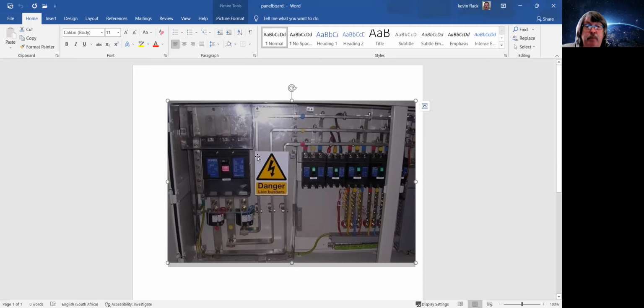If you've got metal plates at the back, I'm not quite sure what's in here. Very important to have that type of thing. You might even find that some people put a Tufnol or an insulation plate below the breaker between the panel and that, so that you enhance the kA area, so there's no conductive material in the zone.